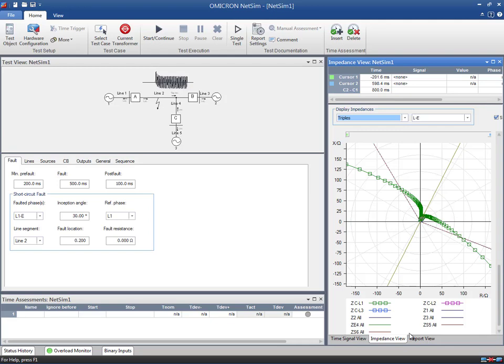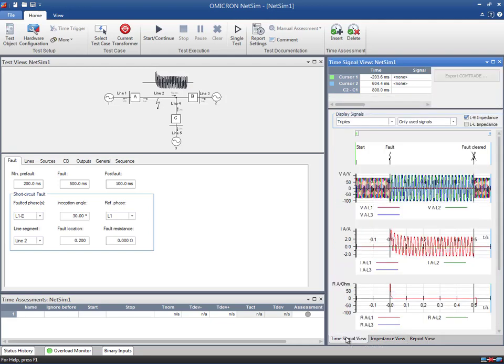Now that we know the basics, we are ready to do our first practical example. We will test the auto-reclosure protection function of the Siemens 7SA6 relay utilized in previous videos. The relay settings will stay the same. Refer to the previous tutorials about the distance and auto-reclosure protection functions as a refresher.